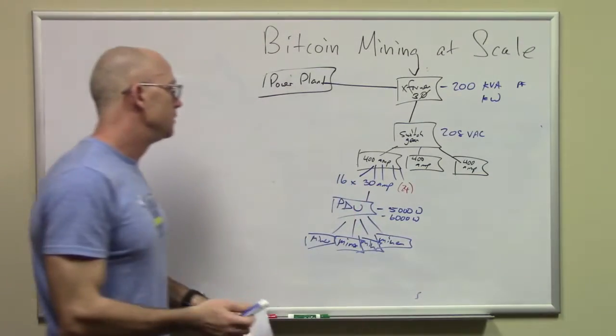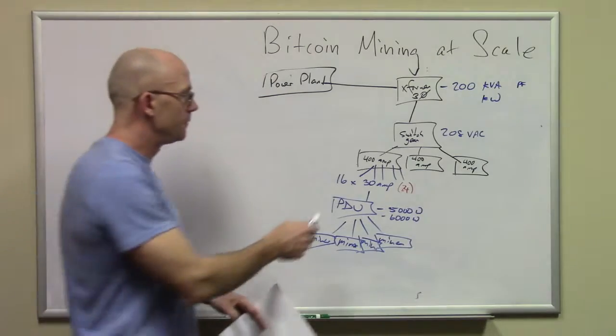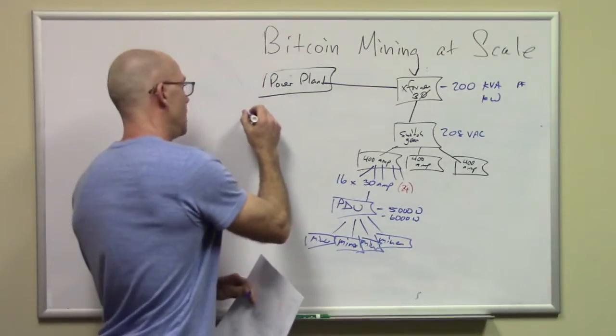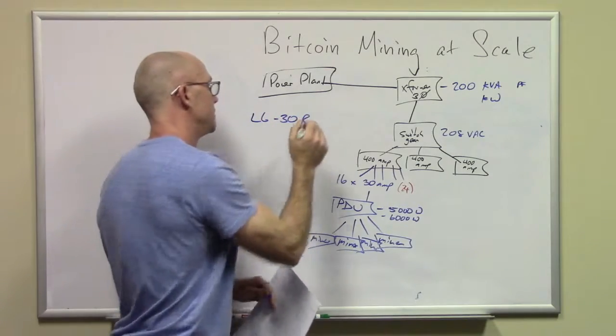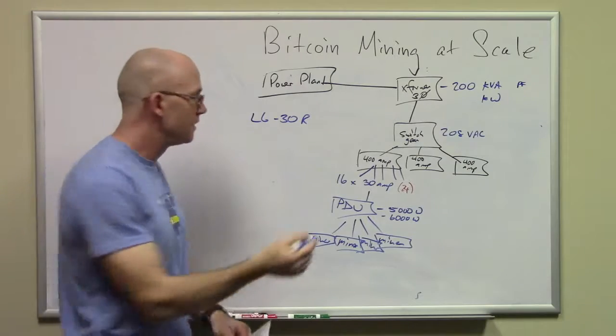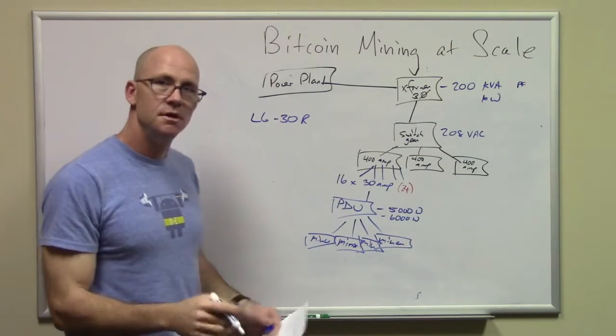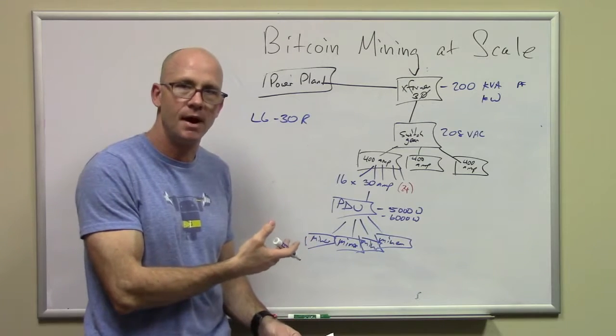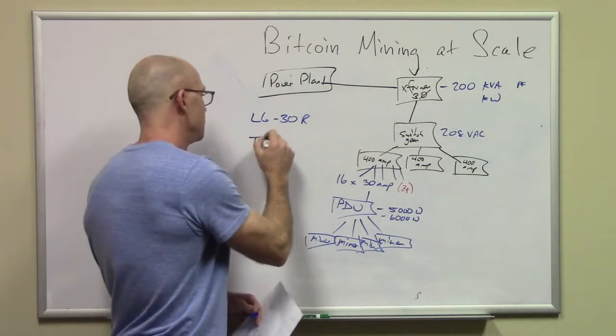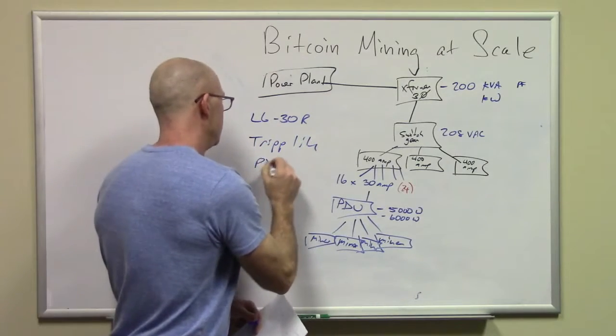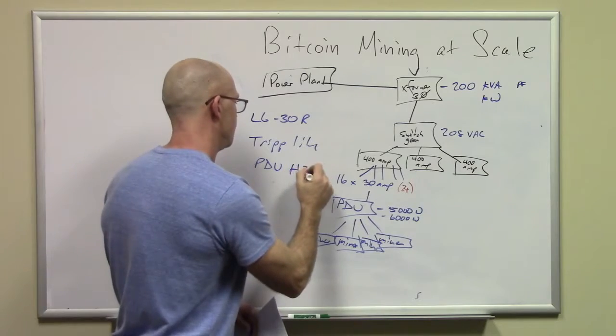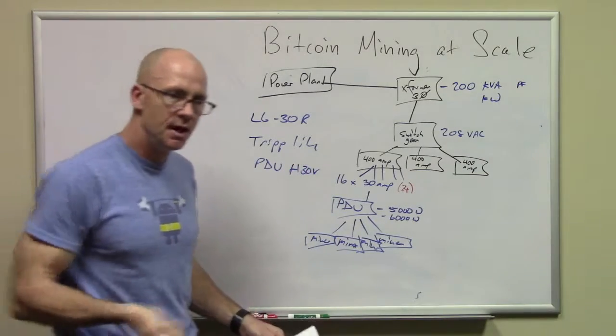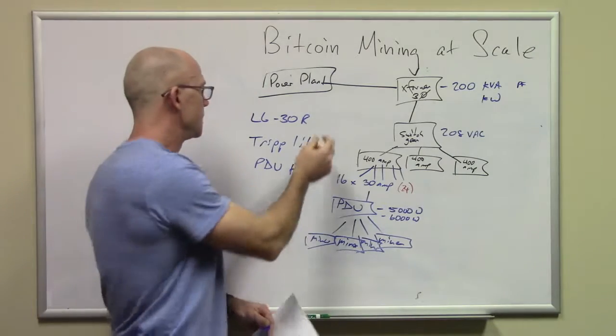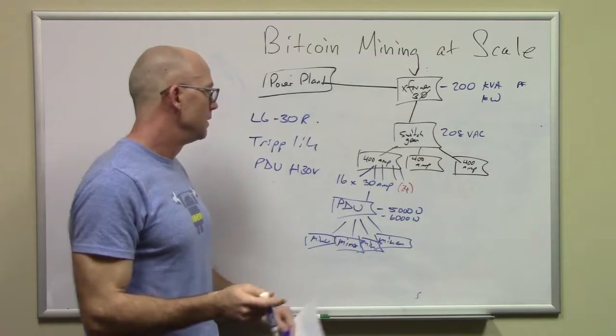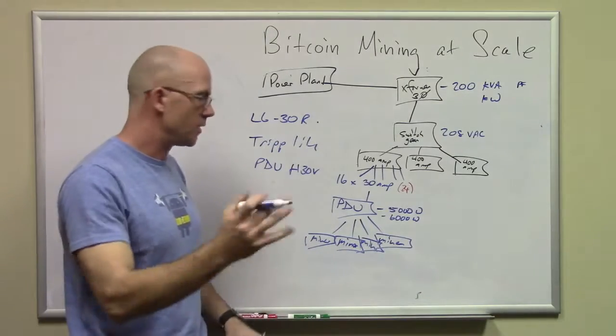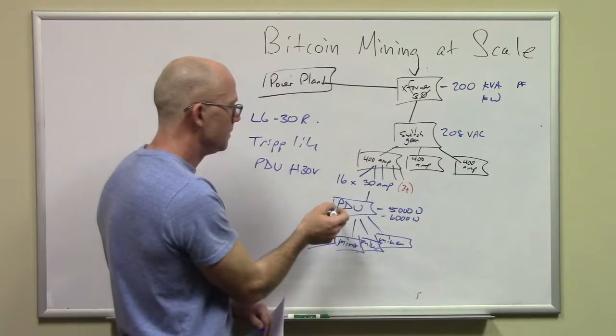Coming out of here, we can do 16 30 amp connectors. I like to use common L6 30R receptacles, so you can get nice inexpensive PDUs, power distribution units—fancy names for big power strips. For example, I like to use Tripp-Lite PDUs, like an H30V model, something like that. It's got 10 little connectors on it and a socket that goes into this receptacle, so if you have a rack of them you can just rack them up. So 16 PDUs coming out of here.